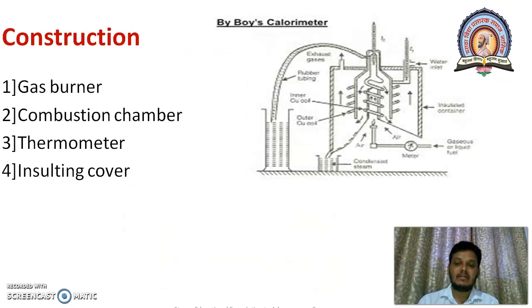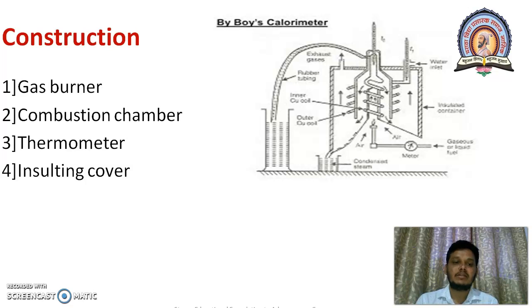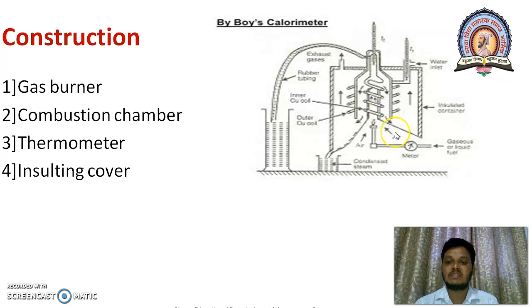Let's start the construction of Boys' gas calorimeter. Boys' gas calorimeter consists of four different parts: the first one is the gas burner, the second one is the combustion chamber, the third one is the thermometer, and the fourth one is the insulating cover. Now let's see the gas burner. At the bottom of the assembly, there is a gas burner in which a known quantity of gas is continuously passed at a known and constant rate — approximately three to four liters per minute.